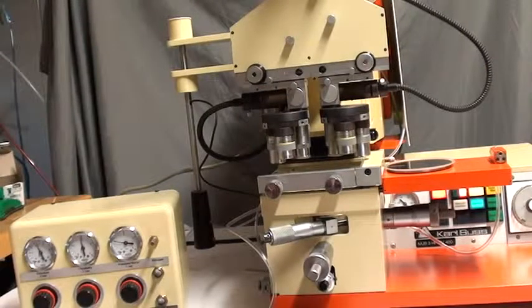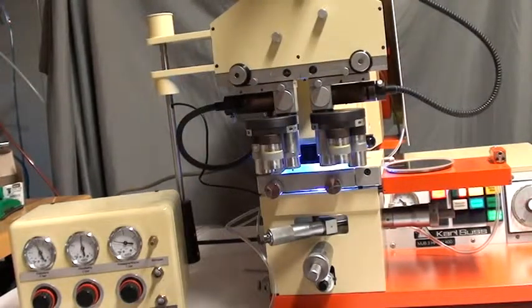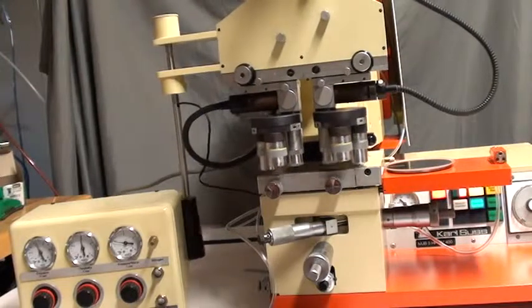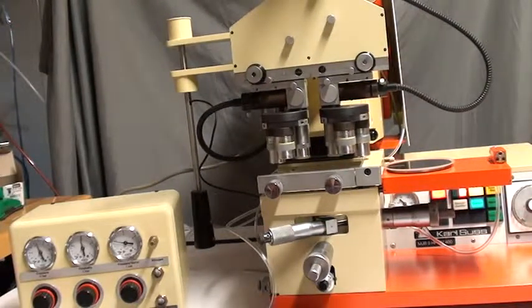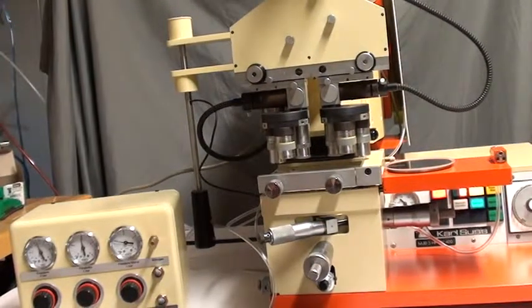This is Class 1's proof of life video for MJB3 serial number 2108, ID number 3841. The machine has been completely refurbished and functioning as originally spec'd by the factory. I will now do an exposure to illustrate the operation. The head comes forward, the shutter opens, and an exposure is taken, and the system sets to the rear again.